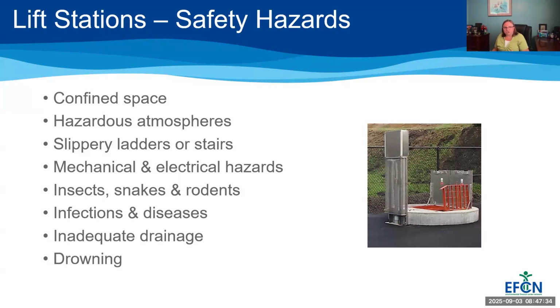So there is a future session on safety, and we definitely want you to tune in, but we want you to know that when you're working with lift stations, you should be working in pairs. You should never be out there by yourself, opening a lift station hatch or pulling a pump or any of those situations. So you should always be working in pairs. You should use radio communication for entry into a lift station. You should definitely understand how to use your gas detectors. You should understand lockout, tagout procedures, all of those kinds of things. And if any of these words sound weird to you or foreign, definitely make sure you're tuning into our safety session at the end of the month.